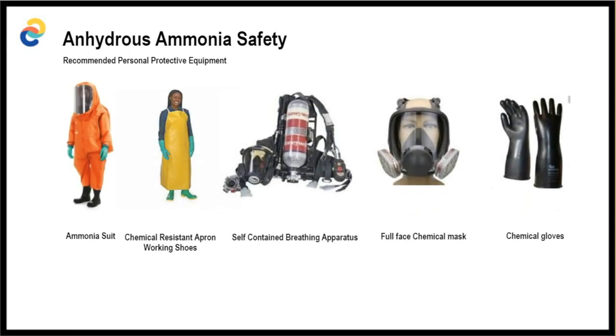Okay. Personal protective equipment should be available at site: an ammonia suit, chemical-resistant apron, self-contained breathing apparatus or SCBA, full-face chemical mask, and chemical gloves. We recommend, depending on the size of the plant, a minimum of 2 units of SCBA and a full face mask. And also during activities, we recommend a 2-person buddy system should there be any handling activities for ammonia.